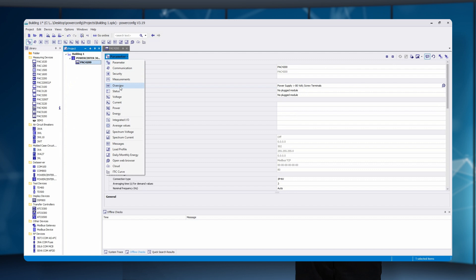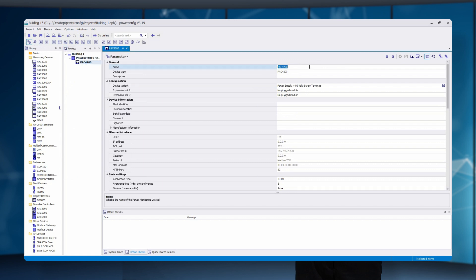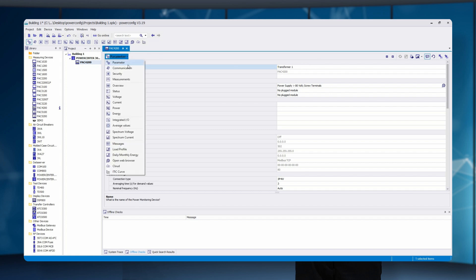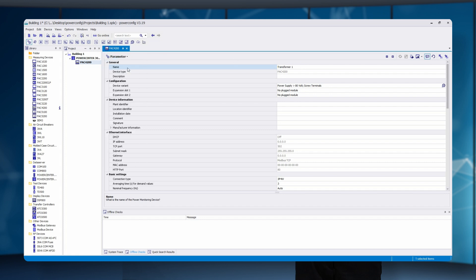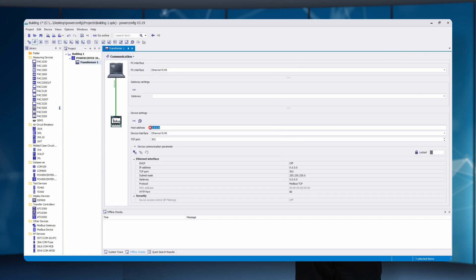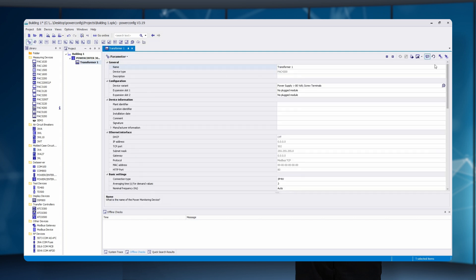First, parameters are assigned to the measuring device. Since this pack measures at transformer1, it is given the name transformer1. Then the communication is selected and the device address is added. In this scheme, relevant data like the IP address are maintained. By ping, the accessibility of the device can be determined. If this is successful, all parameters can now be written down by loading into device.